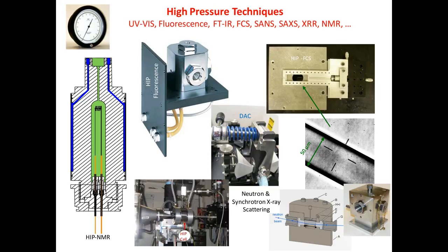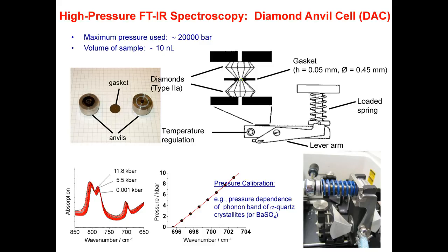For most of these techniques, pressure cells are available, but for about 80% of them you still have to build them yourself. NMR is now available commercially. We have built, for example, a high-pressure neutron reflectivity cell, a high-pressure small-angle scattering cell with flat diamond windows, a high-pressure fluorescence microscopy cell using a quartz capillary, and a high-pressure cell for synchrotron small-angle scattering with flat diamonds. We also use a diamond anvil cell for infrared spectroscopy, with barium sulfate or quartz as pressure calibrants, following the quartz phonon band as a function of pressure.